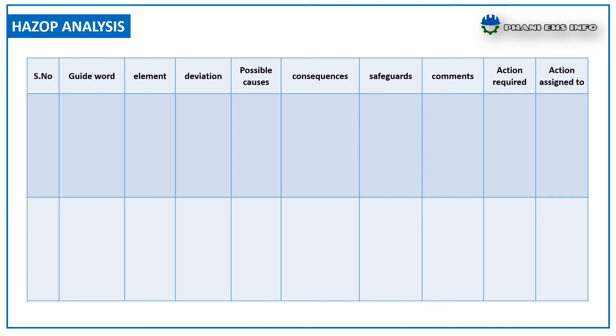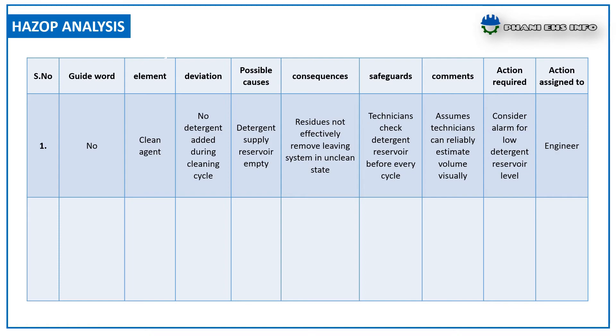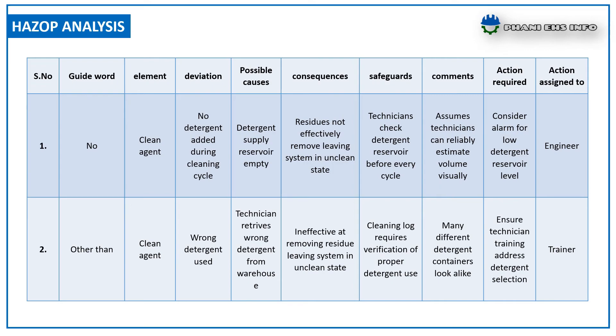Here is an example using a cleaning agent deviation. Guide word: NO. Element: cleaning agent. Deviation: no detergent added during cleaning cycle. Possible causes: detergent supply reservoir empty. Consequences: residues not effectively removed, leaving the system in an unclean state. Safeguards: technicians check detergent reservoirs before every cycle. Comments: assumes technicians can reliably estimate volume visually. Action required: consider an alarm for low detergent reservoir level. Action assigned to: engineer.